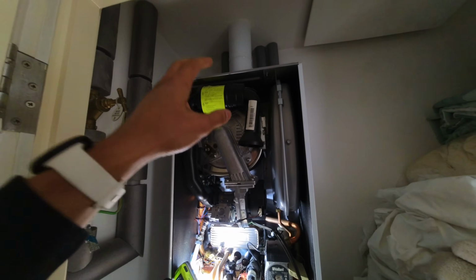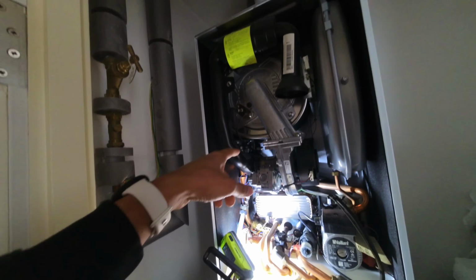That's a nice and easy job. Got the G10 seal, so we're going to take the burner out, have a look inside, see what it's doing, recharge the expansion vessel, check the pressure sensor.